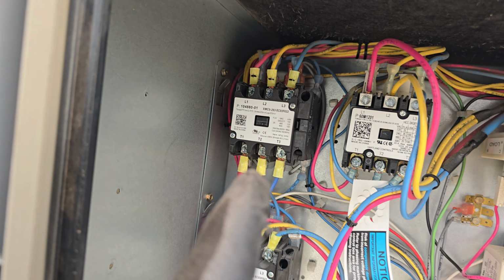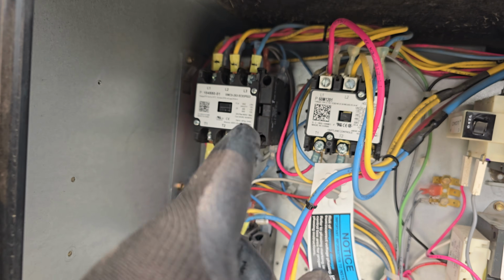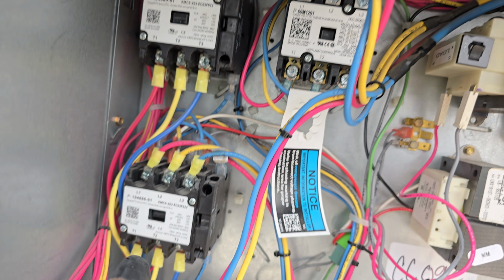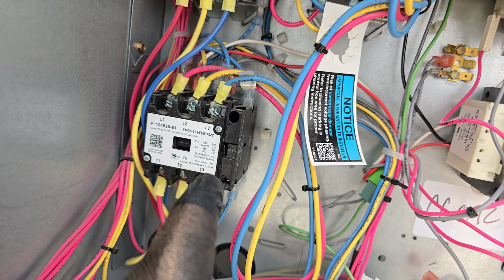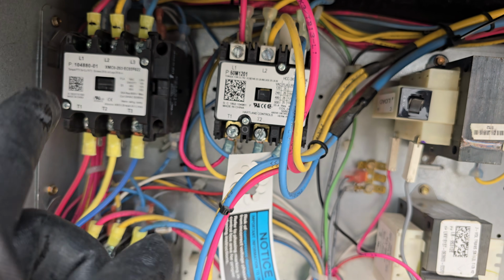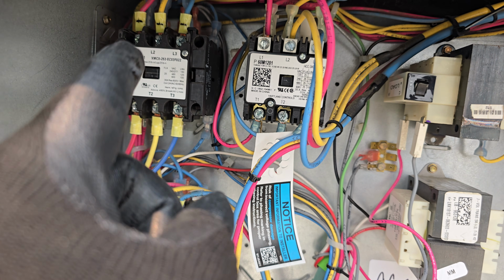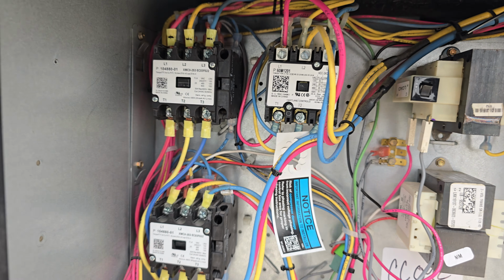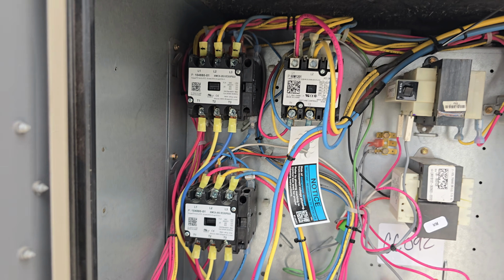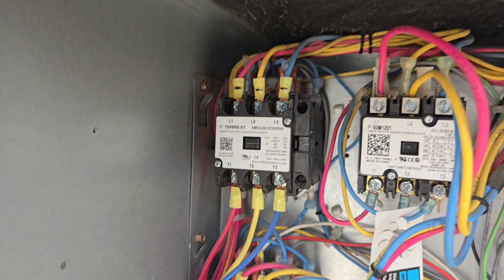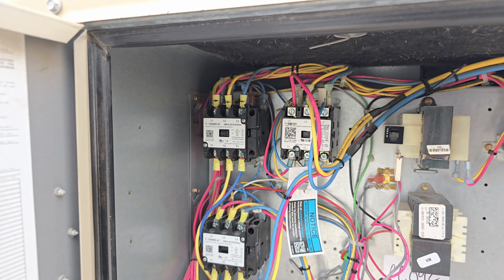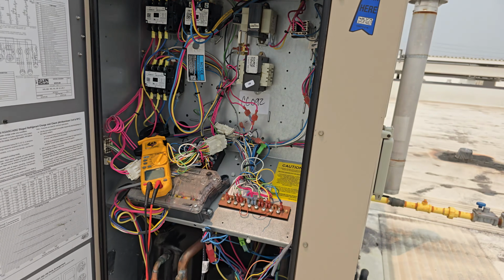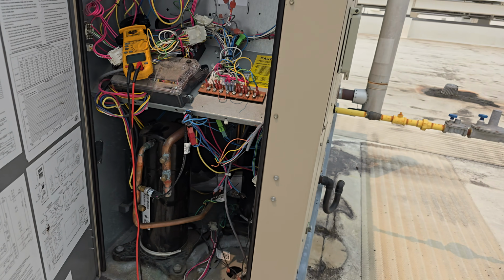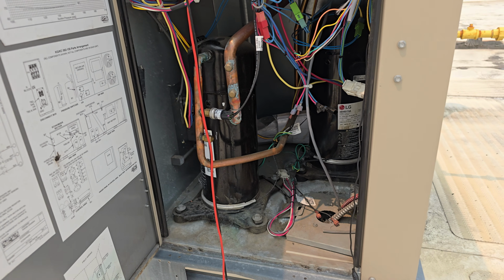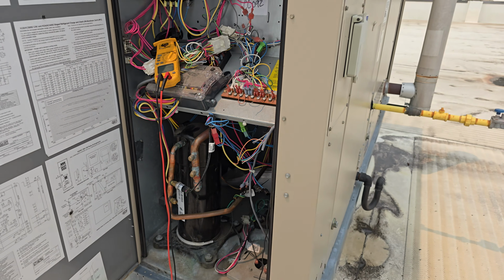First, I'm going to check my contactor. You can see this contactor is energized. This is the compressor energized. This is the blower energized. This one, for compressor number 2, is not energized. So I'm going to turn off the unit and see my contactor and what's going on there. I'm going to check more on this compressor number 2.